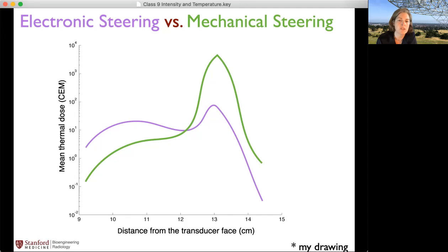as a function of the distance from the transducer face. So their target is out here, and they're looking at the near field as well and plotting the mean thermal dose in the near field. And what they see is that when they do the electronic steering, they have more thermal dose in the near field than they do when they have the mechanical steering, which is really interesting because you might think, well, why on earth would that be different?